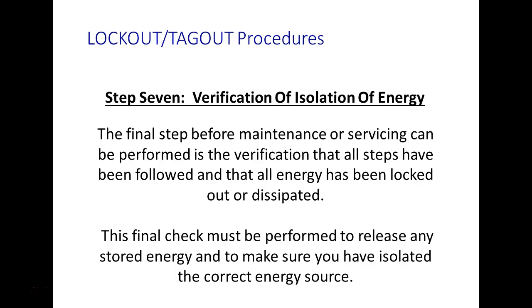Final step for maintenance: verify that all steps have been followed and that all energy has been locked out or dissipated. So just don't take for granted that what you did took out the power, right? You understand that? So you always verify with gauges, with vents, especially pneumatics. Just about every service unit has a little drain on the bottom of it that you can turn. Air comes out of there, so you can not only turn it, but you can also bleed it with it, right? You understand? Pressure gauges. They put a lot of pressure gauges out there on pneumatic systems that you can verify. Of course, electrical, we verify that with what? With the right meter.